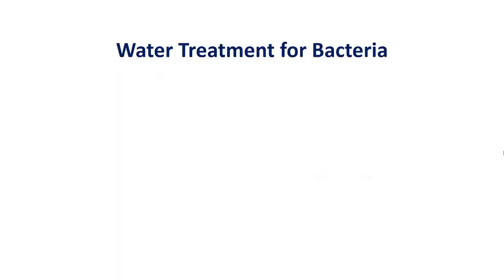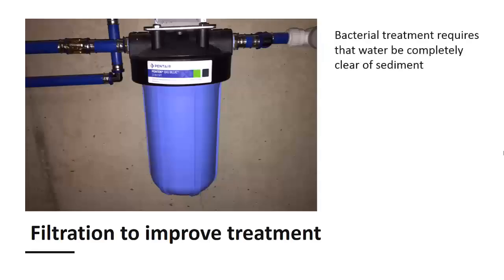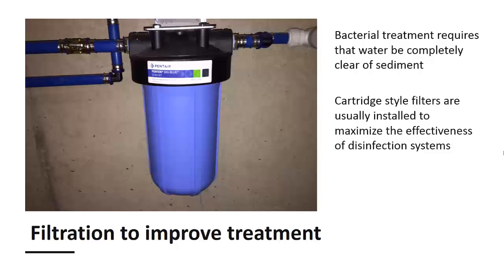Other treatment solutions include boiling, ozonation, ultraviolet light, and chlorination. Boiling is very effective but is not a permanent solution, and ozonation is extremely expensive for household-size units. Ultraviolet light and chlorination are the most common approaches to bacteria treatment for wells and springs. All bacteria treatment requires that the water be completely clear of sediment. For this reason, cartridge-style sediment filters are usually installed first to remove all sediment and maximize the effectiveness of the disinfection treatment. These cartridge filters typically need to be replaced every two to three months, or when water pressure begins to drop as the filter plugs.